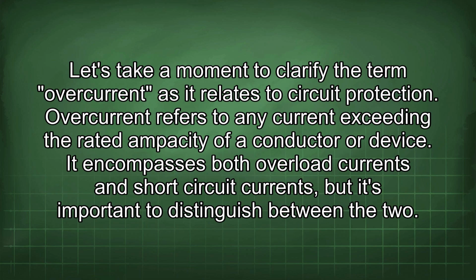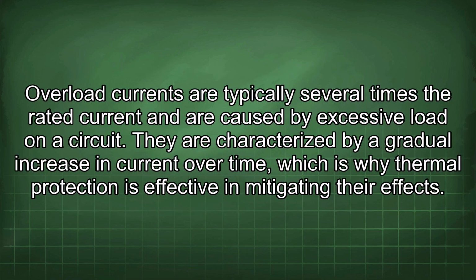Let's take a moment to clarify the term overcurrent as it relates to circuit protection. Overcurrent refers to any current exceeding the rated ampacity of a conductor or device. It encompasses both overload currents and short-circuit currents, but it's important to distinguish between the two. Overload currents are typically several times the rated current and are caused by excessive load on a circuit. They are characterized by a gradual increase in current over time, which is why thermal protection is effective in mitigating their effects.